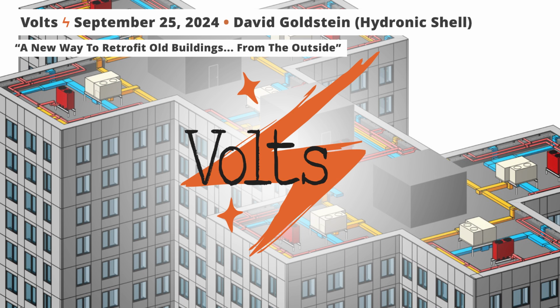Okay, so a couple of heat pumps up on the roof, not unfamiliar. So coming down from those heat pumps to individual window units, and we'll discuss the individual units in a minute, are pipes and ducts. Explain what they're doing and what they're carrying. Yes. So the pipes are doing heating and cooling to the space. They're carrying hot water if the system is in heating mode, and chilled water if it's in cooling mode. Not refrigerants, which is a little bit of a hassle when it comes to normal heat pumps, right? This is all water. Exactly, and that's an important point.